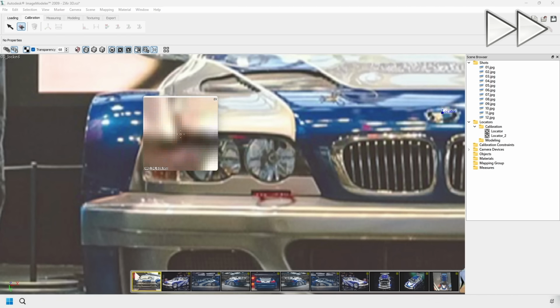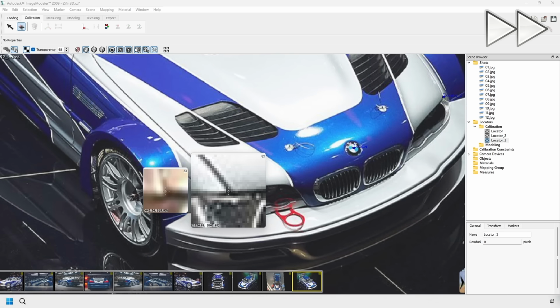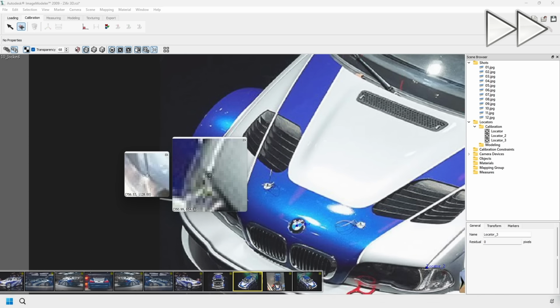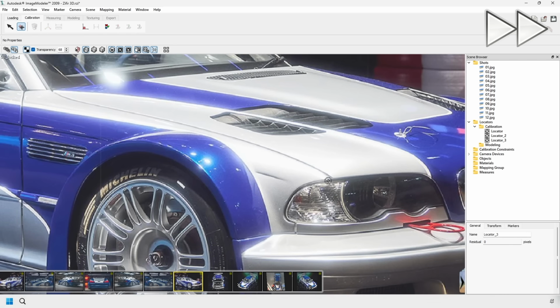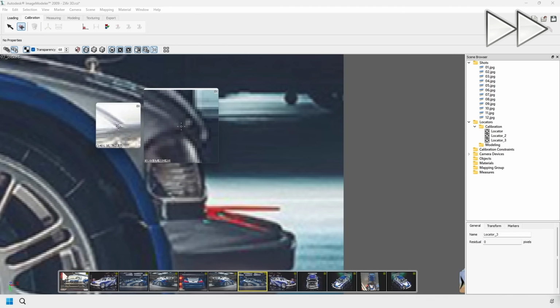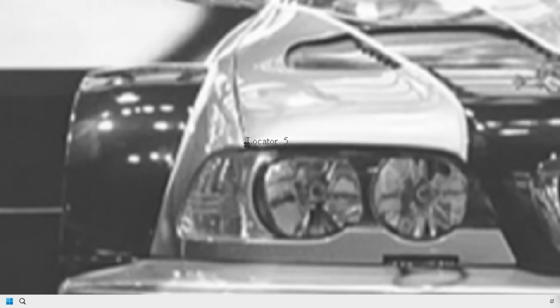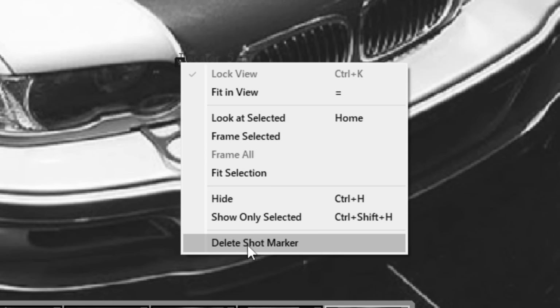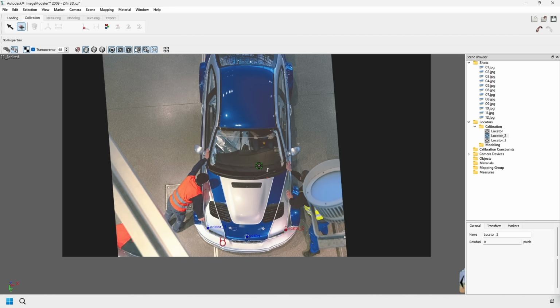Since I'm calibrating in a circle, I'll add a new locator on the other side. It's very important that the number of markers matches the mirrored markers. Now we have 7 markers on each side. If you accidentally placed a marker in the wrong spot and need to delete it, right-click and select the Delete Shot Marker option. You need to add 8 locators for the first calibration.